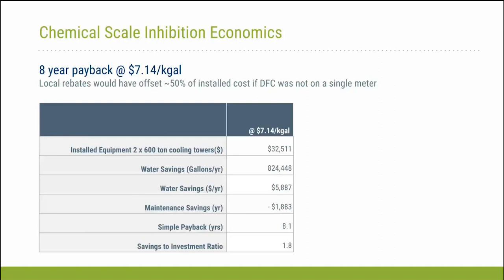The comment there on the local rebates: the Denver Federal Center is a large campus here in Denver, and they have a single point of entry water meter that is used for billing purposes. And although there are local rebates for cooling towers, I think the number was something like only one cooling tower per site is eligible for that rebate, or one system per meter. And so again, the economics could have been significantly improved in other cases, for example, where GSA owns and operates a lot of buildings that do have a single incoming water meter and can capture those local rebates. So I think another thing to keep in mind, if you're installing these, is to make sure to also check with your local water provider and see if there are rebates available.